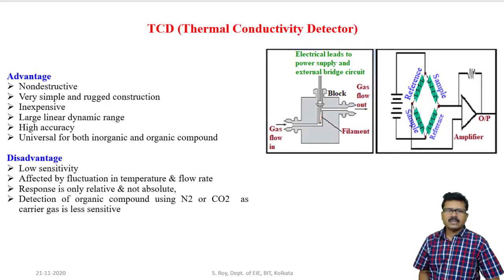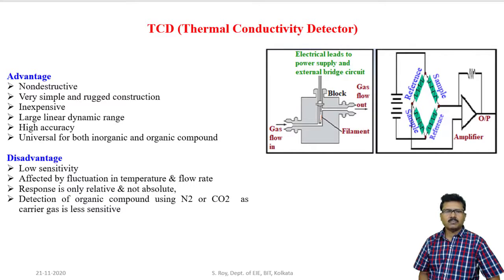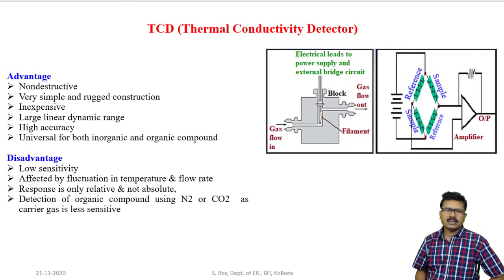Advantages of thermal conductivity detector: it is non-destructive in nature, meaning if we want to use the sample again for further analysis, we can collect it. It is very simple and rugged in construction. It is inexpensive. It gives linear output for a large range. It gives accurate results, and it is universal for both organic and inorganic compounds. Disadvantages: sensitivity is very low. Output is affected by variation in temperature and flow rate. It is very less sensitive if nitrogen and carbon dioxide are used as carrier gas.